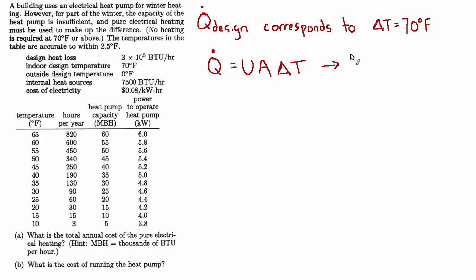So let's start by thinking about the first part. If we're going to find the total cost for the pure electrical heat, we'll need to know the delta between how much is required at each of these temperatures and how much we're actually coming up short using the heat pump by itself. So as a starting point, let's note that the design heat loss, call that q_design, corresponds to the design delta T. In general, we can say that the heat loss equals the overall heat transfer coefficient times the area times the delta T. And that's true for all conditions, not only design conditions. So where we're going with this is we want to identify the heat loss per degree of delta T.